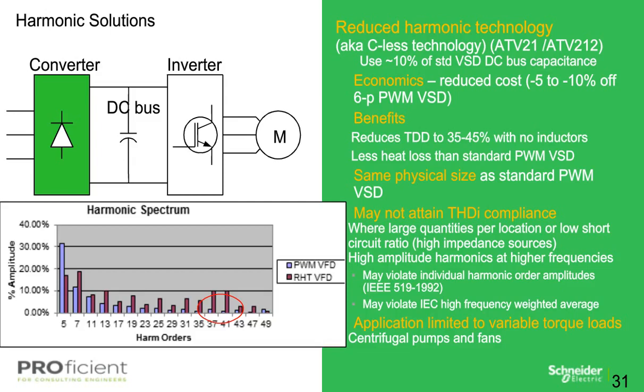So if we take a detailed look at the graph shown below, what we see on the standard pulse drive is very high 5th and 7th harmonic currents, while the reduced harmonic technology, denoted as RHT VFD in purple in the graph, has very flat harmonic current amplitudes, and very high, relatively speaking, compared to the standard pulse drive at the 41st and the 43rd harmonic orders, i.e. not meeting IEEE 519 compliancy. So in essence, IEEE 519 does not only look at the 5th and 7th harmonic order, it looks at the harmonic orders through the entire use of the product. So you truly need to look at the system level and really monitor the device, not only at initial startup, but also at the later harmonic orders, to see how your system is interacting at that point as well.